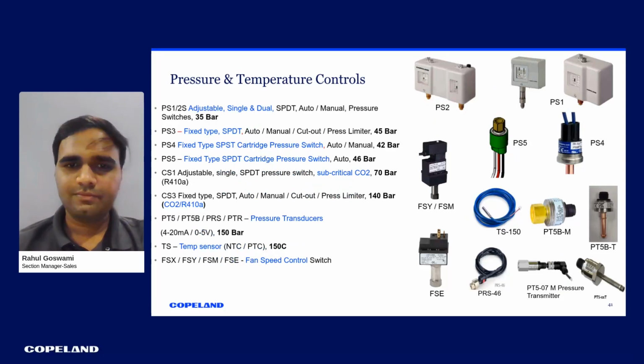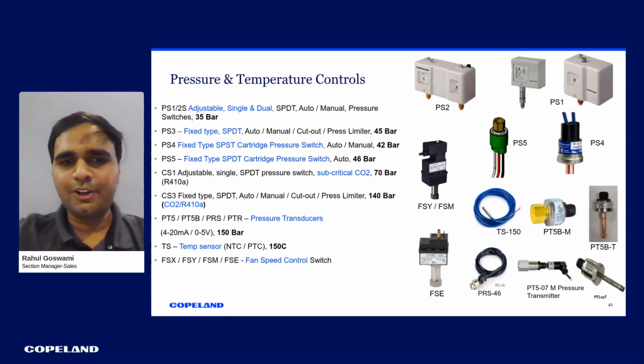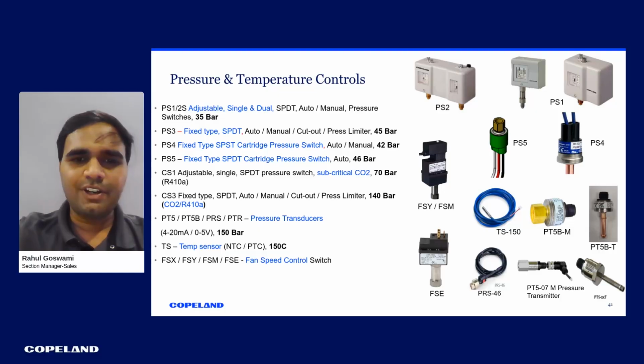Next slide. Coming down to the pressure and temperature controls. Again, first I will cover the pressure part, the pressure switches. We have adjustable and dual pressure switches. These are SPDT auto/manual pressure switches, which can cover up to 35 bar applications. Then we have PS3. The first is PS1 and PS2 pressure switch. Then we have PS3 pressure switches, which have a limitation up to 45 bar.